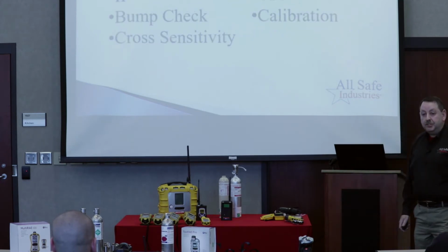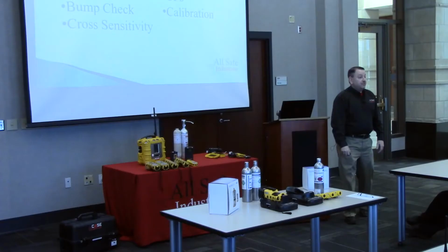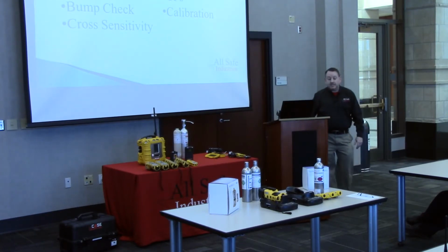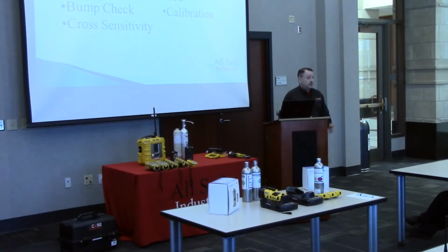So the first thing I like to do is to cover the acronyms. There are several acronyms when you're talking about gas detection. The first being 4-gas. Pretty self-explanatory. 4-gas instruments typically monitor 4 gases simultaneously, and usually that's for confined space entry. OSHA is very specific on the gases that you test when you enter a space. It's oxygen first, then you check for flammable gases, and then you check for your toxic gases.